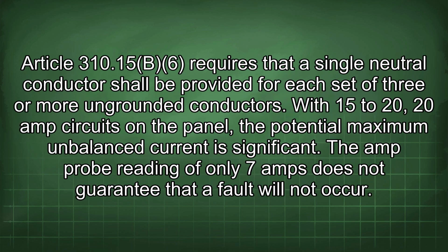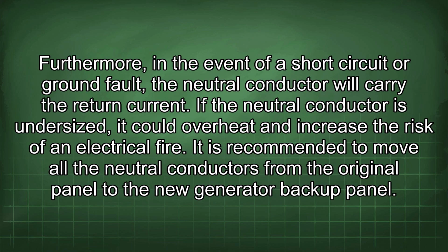Article 310.15(b)(6) requires that a single neutral conductor shall be provided for each set of 3 or more ungrounded conductors. With 15 to 20, 20 amp circuits on the panel, the potential maximum unbalanced current is significant. The amp probe reading of only 7 amps does not guarantee that a fault will not occur. Furthermore, in the event of a short circuit or ground fault, the neutral conductor will carry the return current. If the neutral conductor is undersized, it could overheat and increase the risk of an electrical fire.